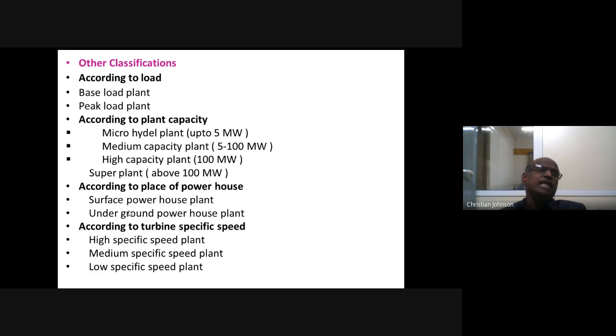One of the major advantages of the hydropower plant is its instantaneous, immediate start and immediate stop. Comparing hydropower plants with thermal power plants, thermal power plants take a lot of time for warming up. In order to bring the power to the grid, you have to wait about 6 hours, because the coal has to be brought from the mining and may be dumped in the coal yard.